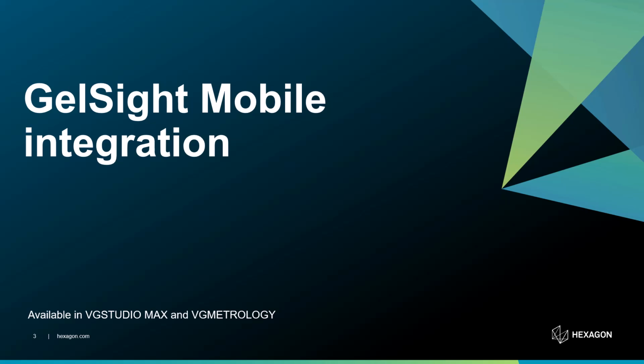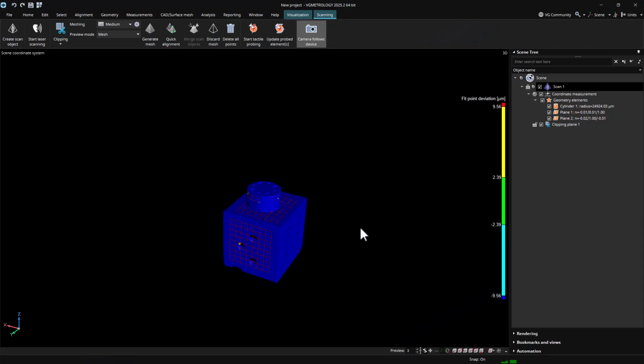Version 2025.2 also introduces support for another type of hardware, the third-party GelSight Mobile Tactile Sensor Kit that can be used to measure, visualize, and inspect the 3D topography of surfaces in very high resolution. By attaching the sensor to Hexagon's Absolute Arm, it is possible to acquire detailed surface patches that are positioned correctly in relation to other representations of the inspected part, like a CT volume or a surface mesh.